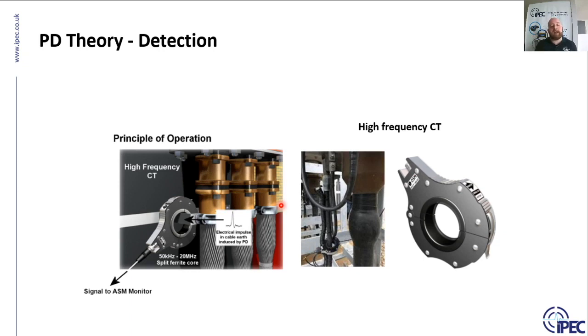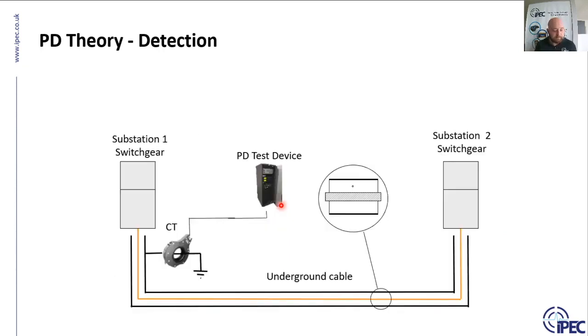So for underground cables, we use a HFCT, high frequency current transformer, and that HFCT, they come in different shapes and sizes depending on where they're going to be applied, and we can apply the HFCT to cable earth sheath. We also apply the HFCT around the core of the cable, and I'll explain why next. So in this example, I've put the HFCT on the earth sheath here, but you could also install the HFCT around the core of a cable there. But importantly, the HFCT needs to be installed on one or the other. It cannot be installed in a place where you're capturing both.